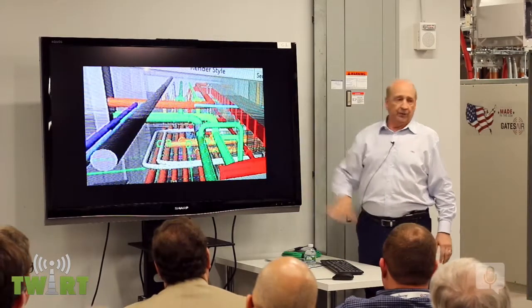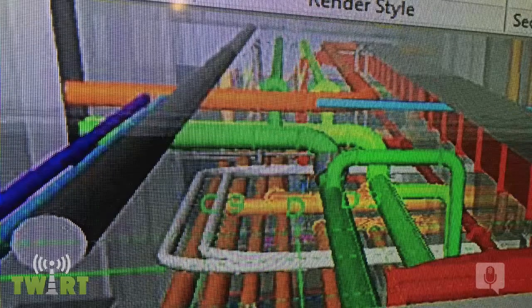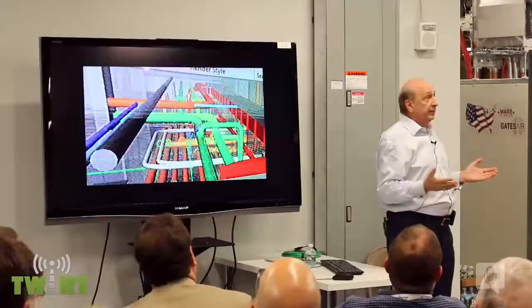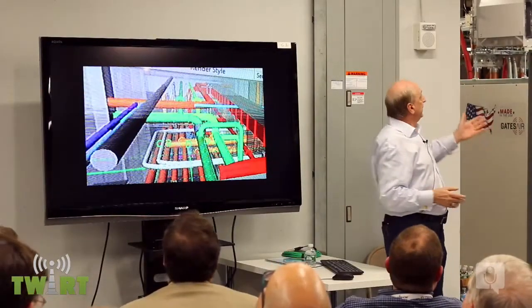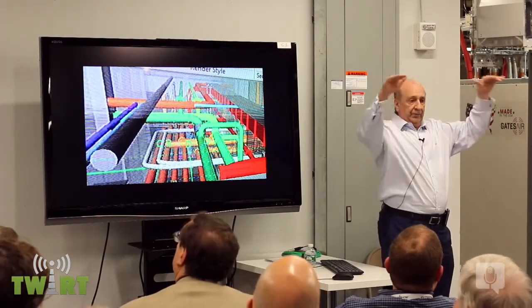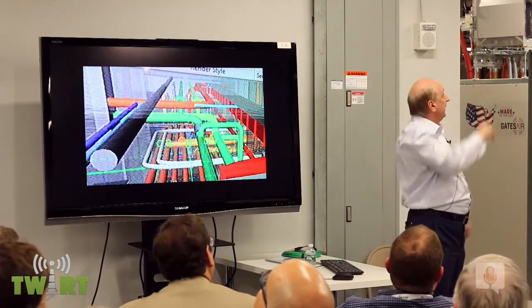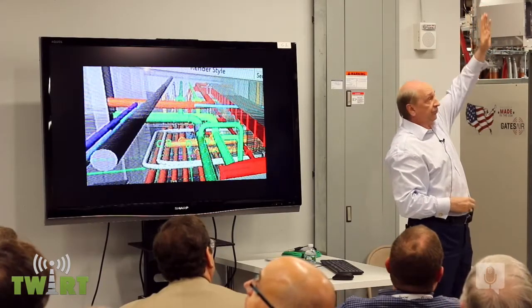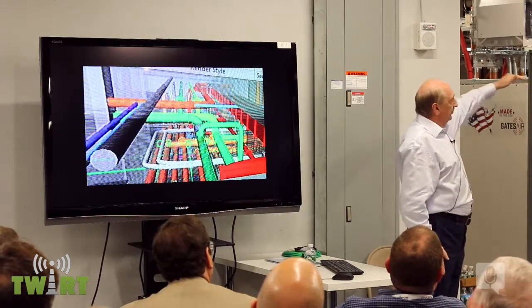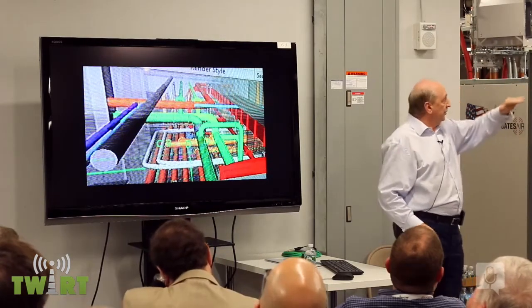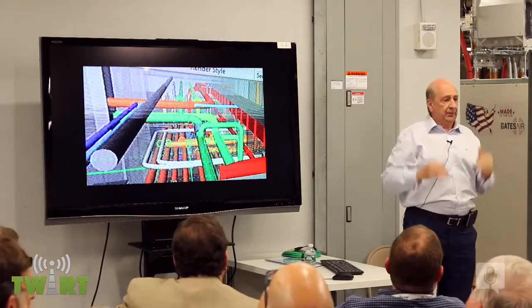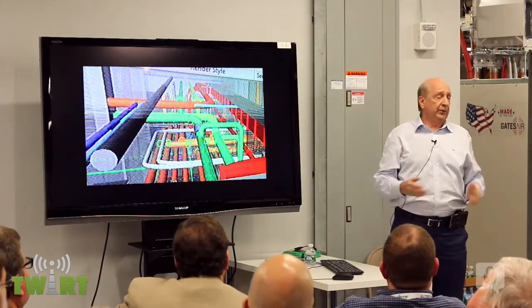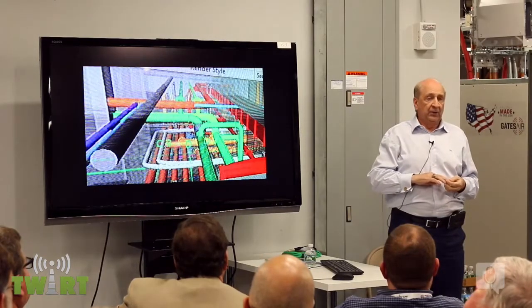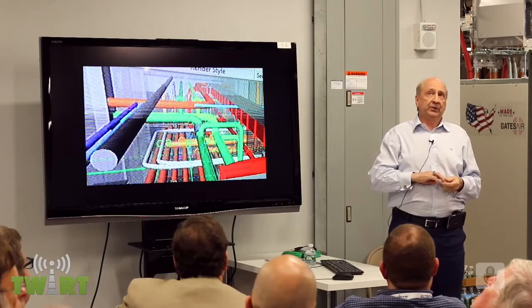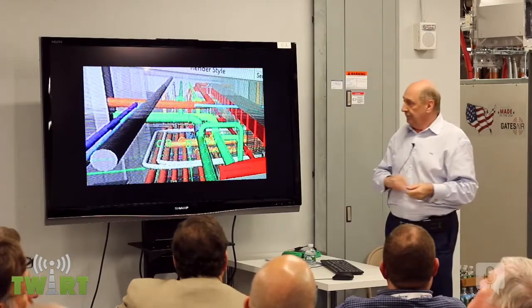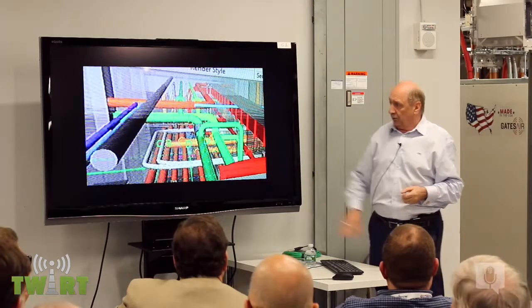Everything was 3D rendered for the whole job, with about 23 vertical feet above me, 17 above me here. Everything had to be in proper layers so it could all pass by each other: the water all at the same height, the electric feeds including the 13.8, all the transmission lines across the floor, and all the duct work layered in to make sure it would work. Having a 23-foot ceiling made this possible; with a normal height ceiling, it would have been an impossible task. So we had an architectural firm do all the 3D modeling.